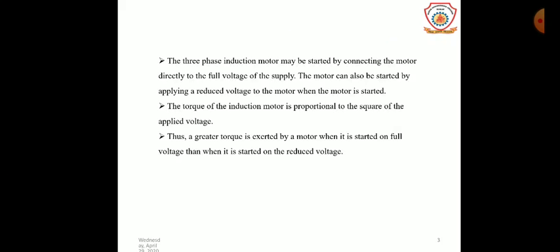The three-phase induction motors may be started by connecting the motor directly to the full voltage of supply. The torque of an induction motor is proportional to the square of the applied voltage, so a greater torque is exerted by a motor when it is started on full voltage than when it is started on reduced voltage.